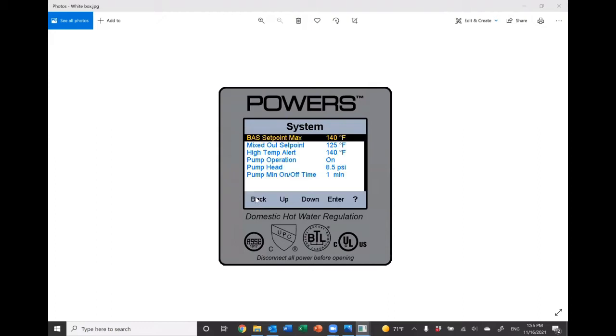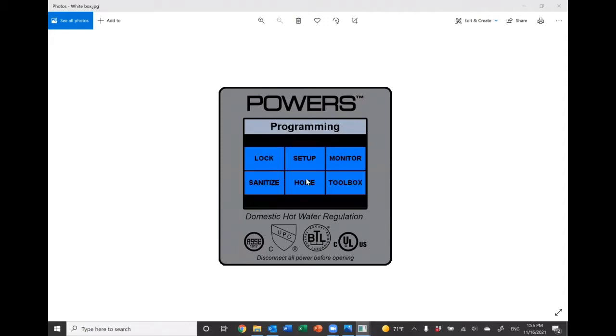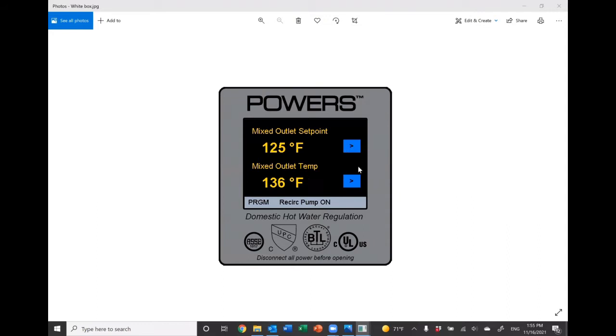So once you've got all those programmed in, you just go back out, you can go to your home screen. It's going to show you your mix set point and what your actual mix temperature is on the outlet there. You can toggle through these and see your hot supply temp, your cold supply temp, your recirc return temp, your pressure on the mixed outlet, your hot side pressure, your cold side pressure, your recirc pressure. All this data is going to help you diagnose if you're having an issue with the system, so that we can diagnose it and then come up with a fix on it.